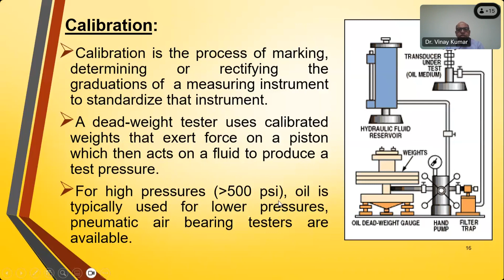So for calibration, we need a deadweight tester or any high primary standard or any high accuracy instrument to calibrate the instrument. And all the standards in India are kept in the National Physical Laboratory. I worked there for 5 years on different standards. So everyone has to calibrate their instrument in the National Physical Laboratory. All the parameters are there to calibrate. For low pressure, we use air, and for high pressure, more than 500 psi, we use oil.